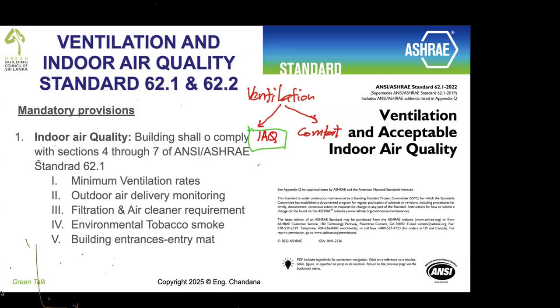We need outdoor air into the building if occupants are in the zone. Places where no occupants, we don't need outdoor air. What purpose? To purge bad odor, impurities, pollutants, also supplying a little bit of oxygen. So we'll have to calculate minimum ventilation rates. This standard helps you to calculate minimum ventilation rates, and we'll have to comply. And this is being used in Sri Lanka. As a chartered engineer, you cannot sign for designs without minimum ventilation rates.